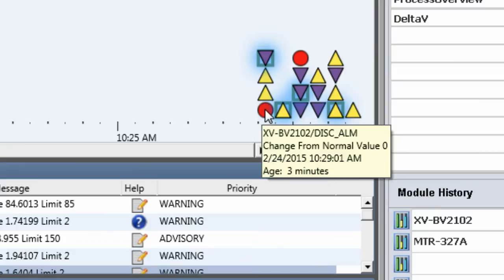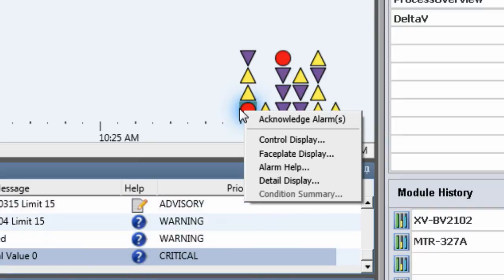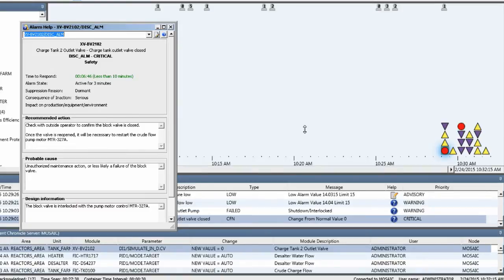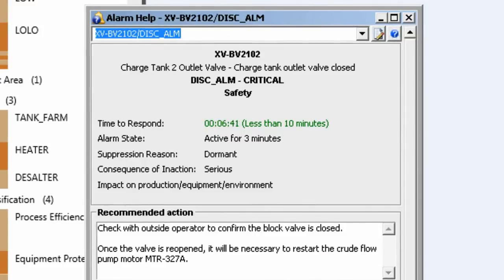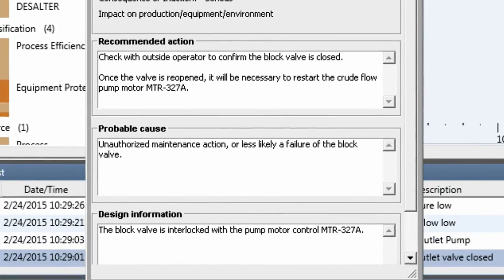Now that we have a good sense that the problem is in the tank farm and that somebody closed a block valve, let's see what more Alarm Mosaic can show us. The first-out alarm was the block valve. I'm going to right-click on it to open a context menu, from which I can do a number of things — one of them is Alarm Help. This is where the operator can read the prepared instructions for that particular alarm. The first action recommended is to check with the outside operator to confirm that the block valve is closed, and once it's reopened, to restart the crude flow by turning on a motor.